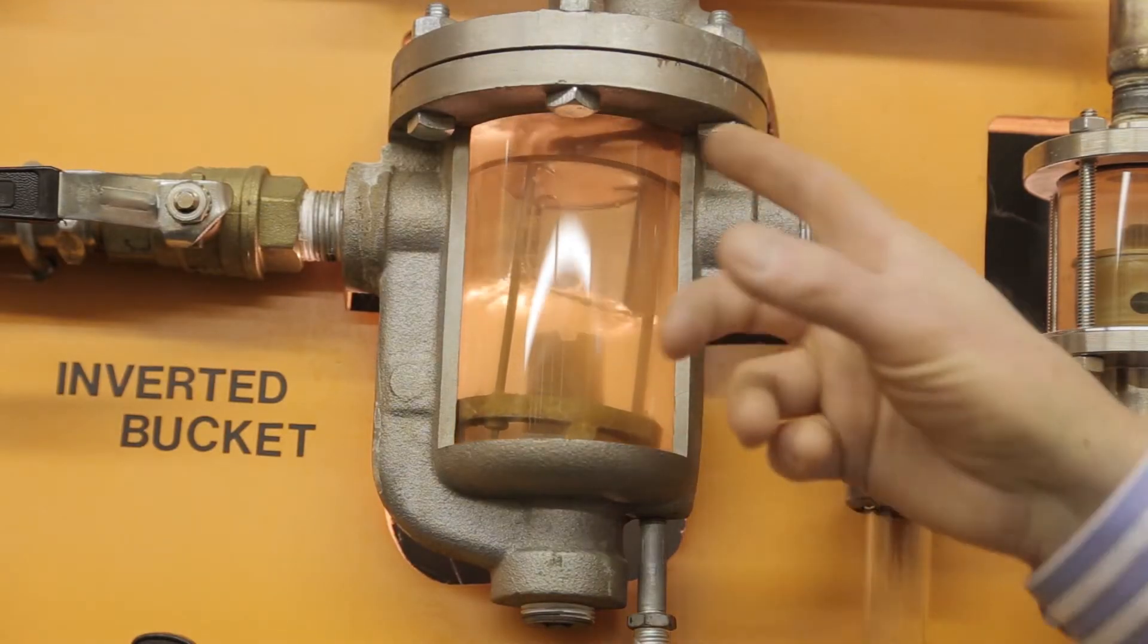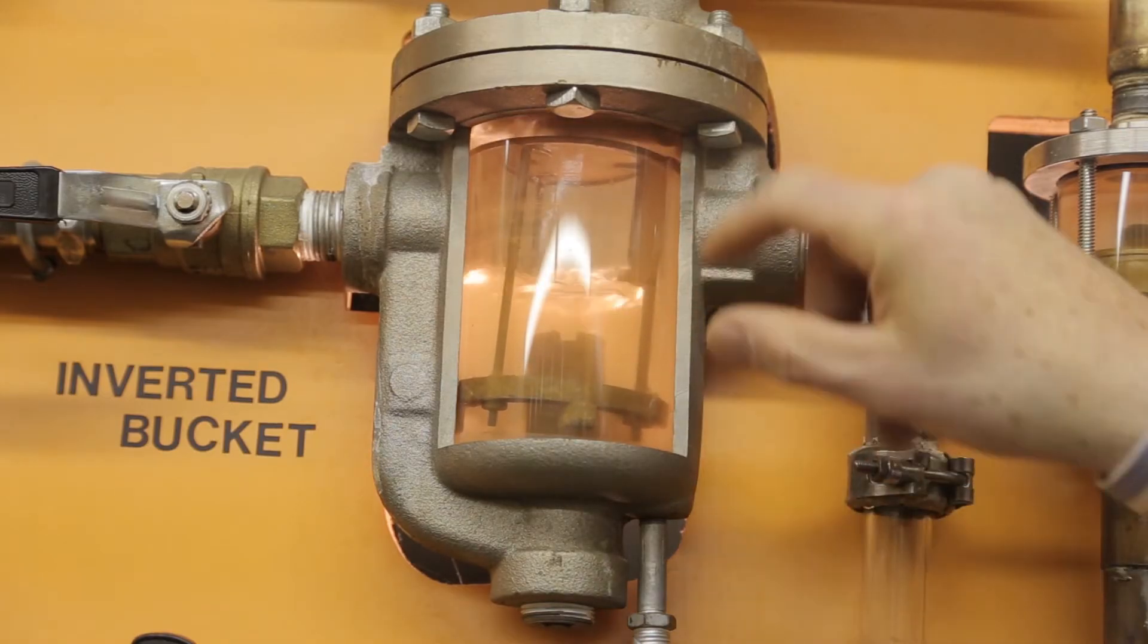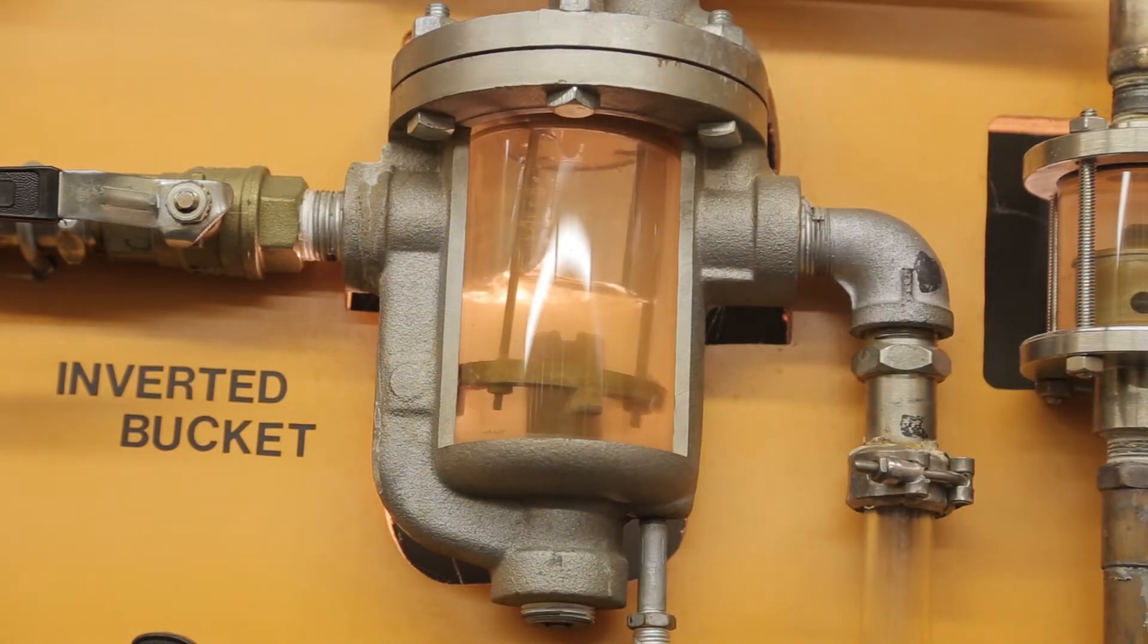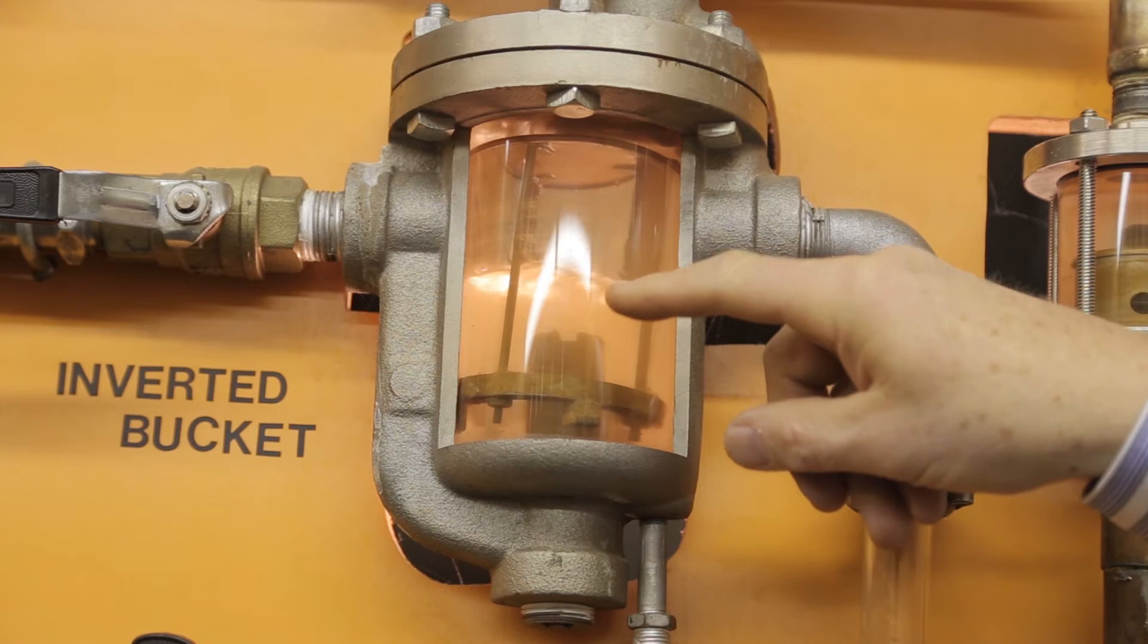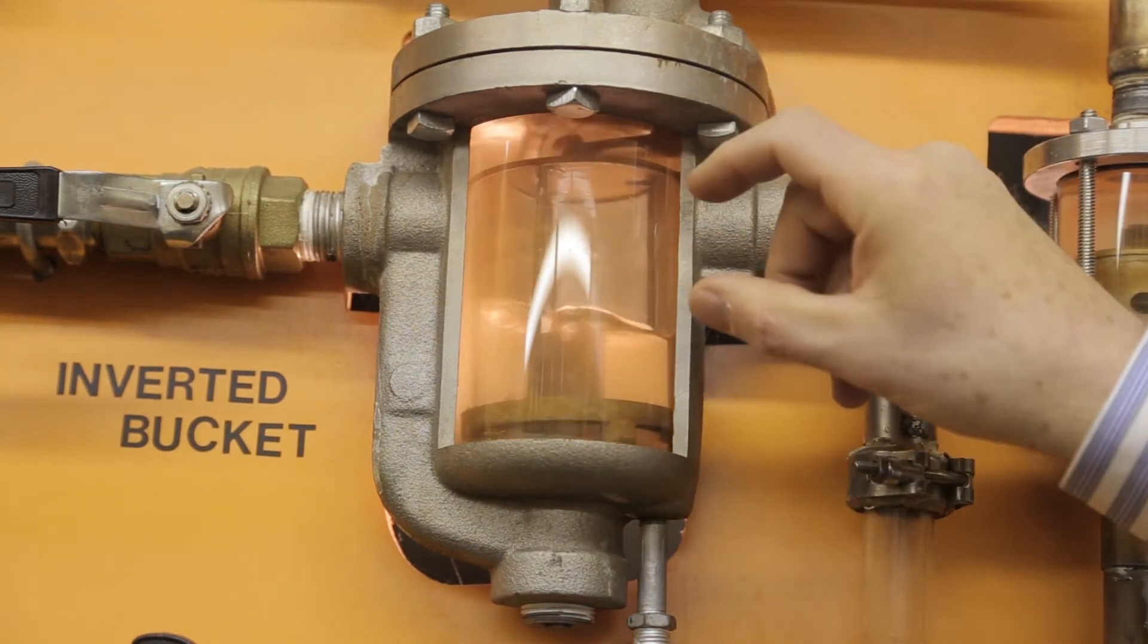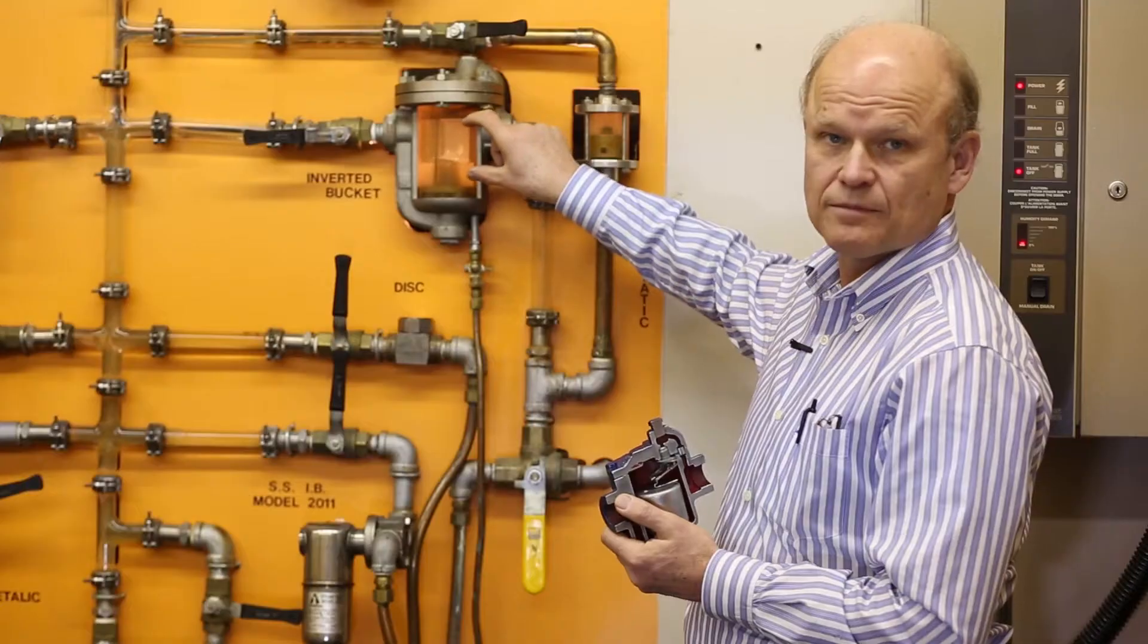It has steam underneath the bucket. The entire trap body is completely filled with condensate, and as the trap fills up with condensate and becomes about one-third steam in the bucket, it loses its buoyancy. The bucket falls, condensate flows out around the outside and down until it gets to be about two-thirds full of steam and the bucket refloats itself.